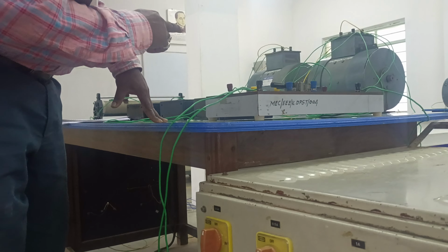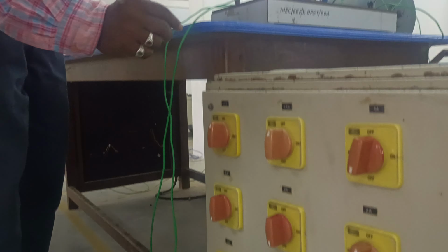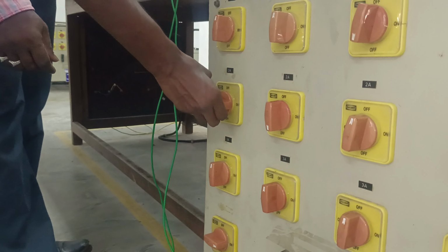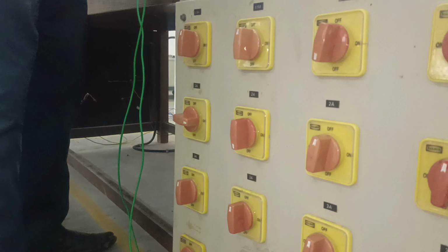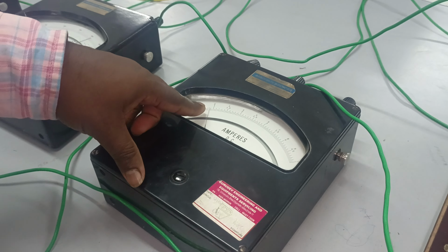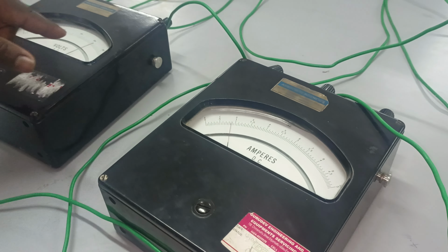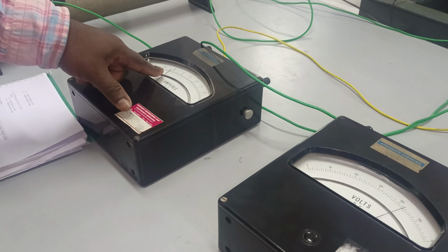Here the rated current of the generator was 10 ampere. So you can apply one by one. You can apply the 2 ampere load, and in parallel you can measure the ammeter reading. You see that the 2 ampere load was applied. Here the reading of 1.9 came. Similarly the voltage and the field current are also getting reduced. So here all the readings have been noted.